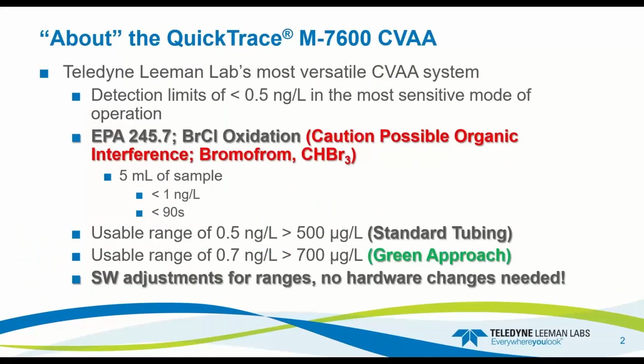The QuickTrace M7600 is our most versatile system, so you can actually hit instrument detection limits, method detection limits of less than 0.5 ppt, nanograms per liter. It is sensitive enough to work with EPA 245.7, but we don't recommend it because in certain cases you can form bromoform, which will give you a false bias in the results. It could be anywhere from 10 to 200 ppt of false bias on samples when that's formed. But without that, we can easily hit 1 nanogram per liter in less than 90 seconds with this system.